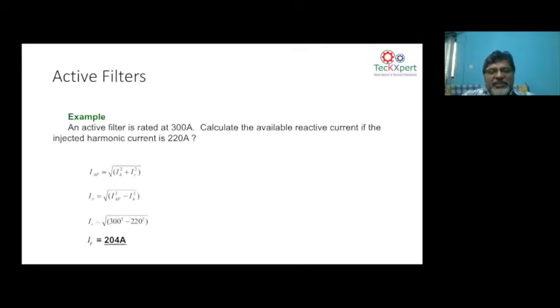So what it shows is, if you have a 300 ampere active harmonic filter, and you have a harmonic current of 220 amps, that means this active harmonic filter can give you 220 ampere of harmonic current, and it can also give you 204 amps of reactive current. That means with 204 ampere reactive current, you can use it for power factor correction. That is how an active harmonic filter does the double function of power factor correction and harmonic filtration. So if you correctly size the active harmonic filter, sometimes you may not need a capacitor bank.